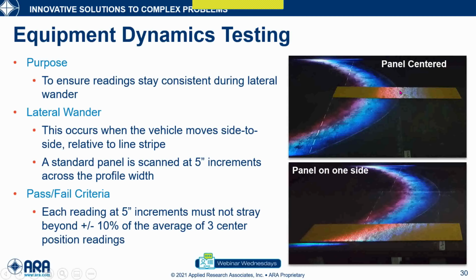So we measure that, and then we move this panel to the right and left at 5 inch increments. So we move it to the left 5 inches from the center, then the next 5 inches, that will be 10, 15, and so on and so forth. Once we do that, the criteria is that we average the 3 center readings that we obtain here and compare it with the movement on either side. The criteria is that it has to be within 10% of the average of the 3 center position readings. So this is what we do in the lab to simulate lateral wander, and like I said, all the units that do data collection need to pass this test.